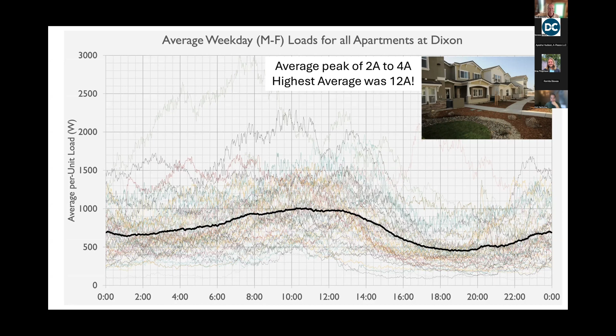So in the real world, people are going to be between 2 and 12 amps, and we're putting in 100 amp automatic transfer switches and redesigning apartments to fit that by code. If the code reflected reality, the panel capacity would need to be about 90% less than this, because this is how people actually use power. So we're pretty confident this is going to work out.